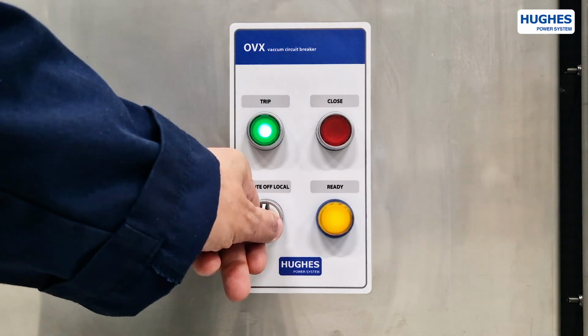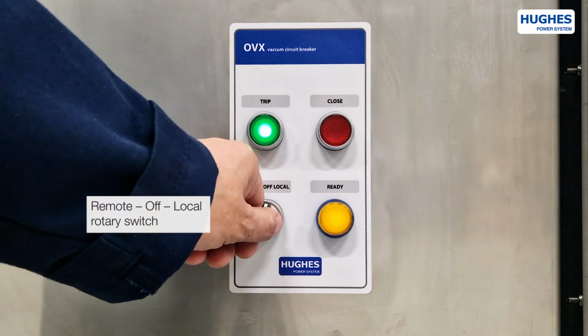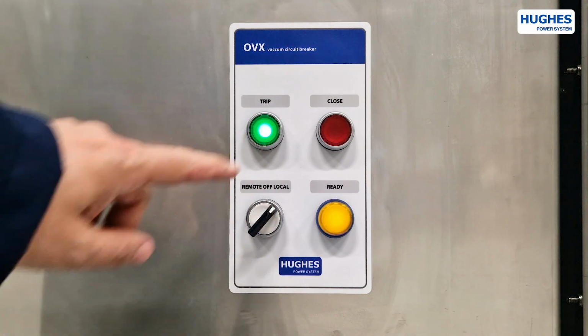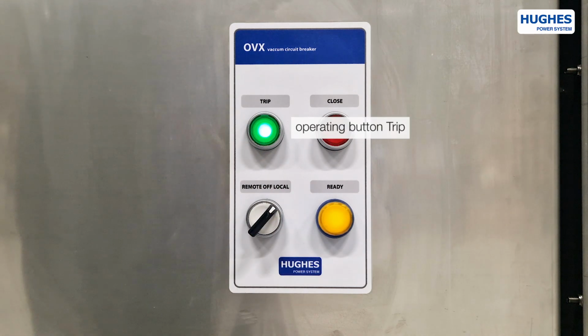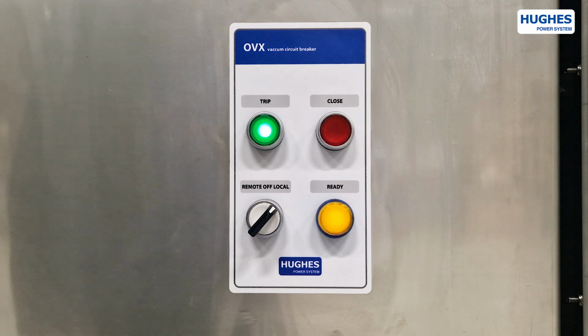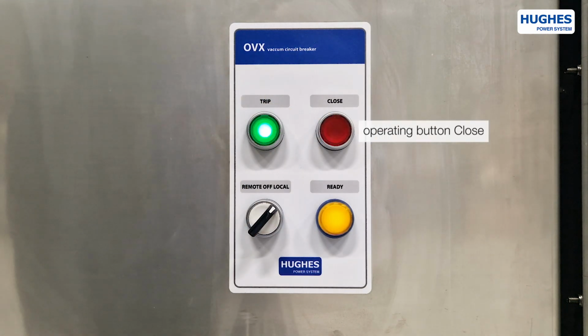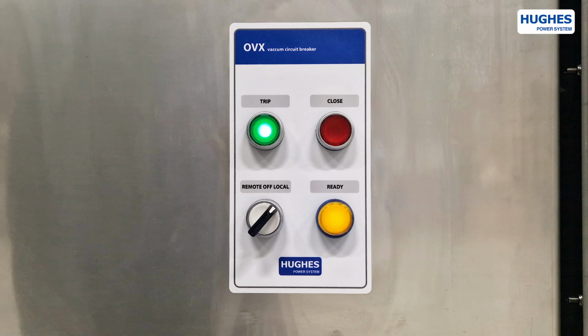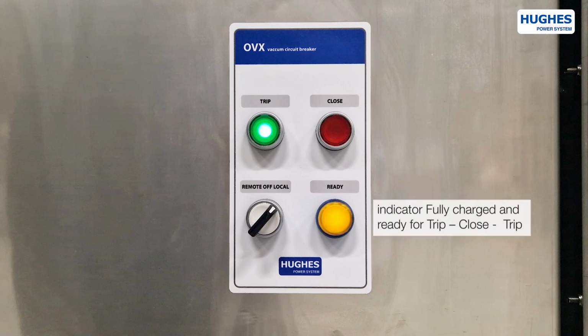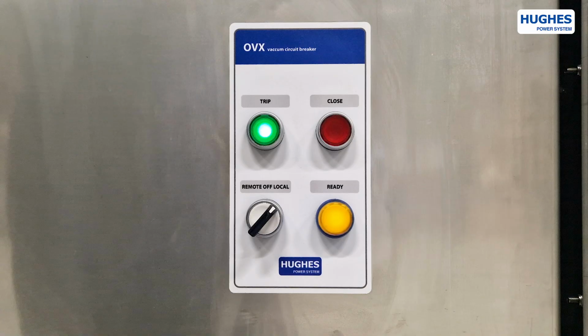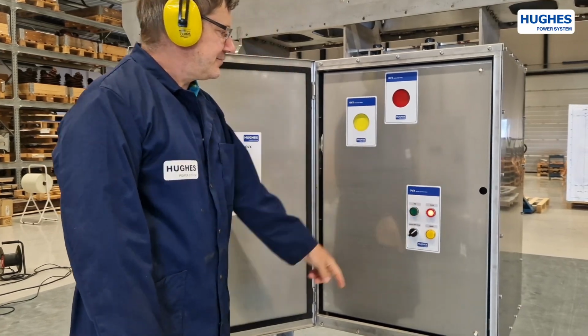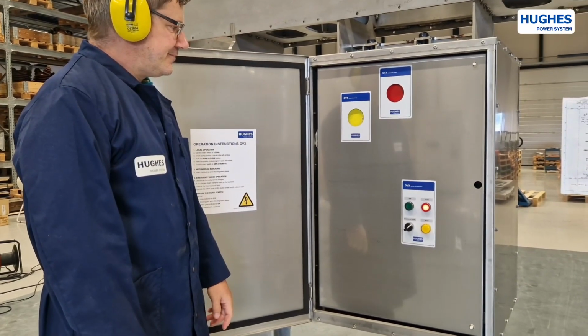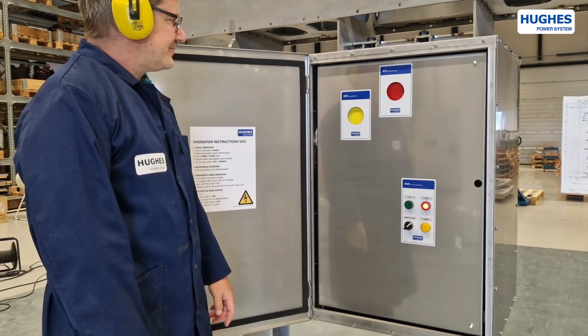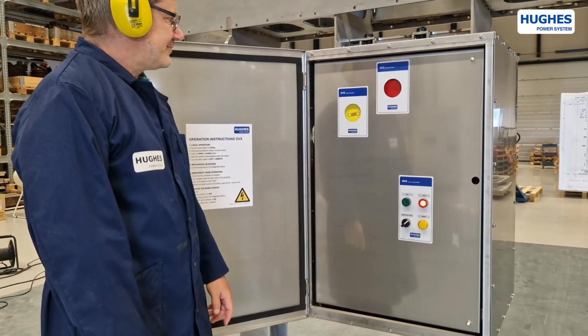The first rotary switch is the remote off local switch. The upper left green push button indicator operates the switch to trip and indicates the switch position. The upper right red push button indicator operates the switch to close and indicates the switch position. The lower right indicator lamp indicates the spring operation mechanism is fully charged and ready for a momentary trip-close-trip operation. Operation buttons can be supplied with a safety timer from 10 to 120 seconds.